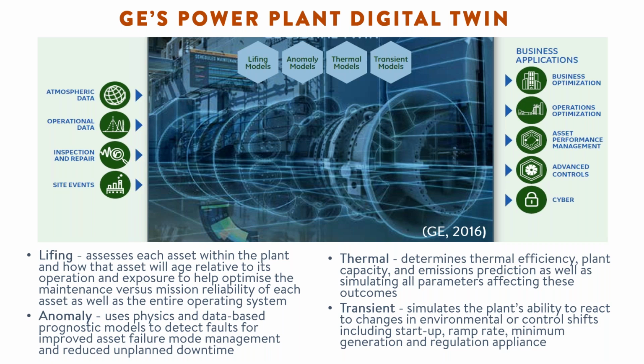This slide shows an example of a power plant digital twin developed by GE. It integrates a collection of high-fidelity, computational physics-based models and advanced analytics that focus on various areas of power generation processes. GE claims that applying its digital twin can unlock up to 8 to 13 megawatts of capacity from improved plant efficiency, reduce startup time by up to 50%, and reduce unplanned outages, saving the generator up to $100 million per year.